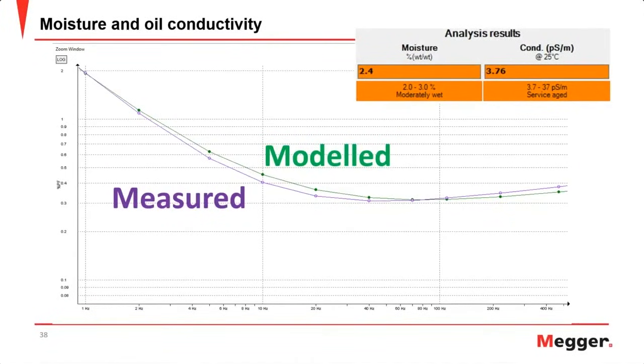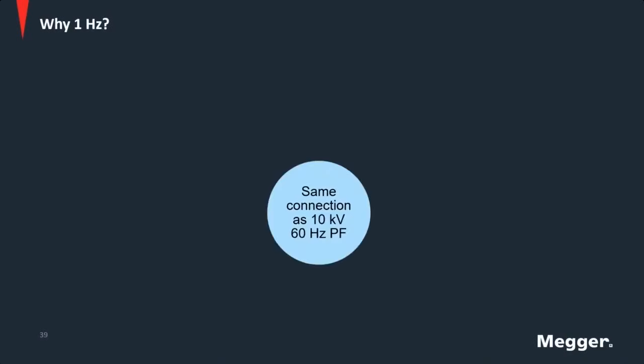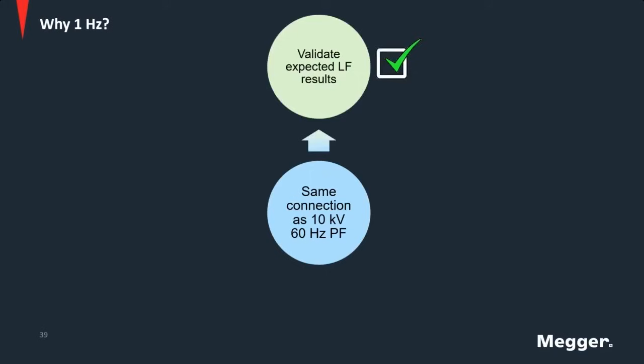What we have found is that instead of using this entire dielectric frequency response range, we can hone in on the 1 Hertz value. And the 1 Hertz can tell us a little bit of information. And when we look at 1 Hertz, what we can do is, using the same connection that you're already using today for your 10 kV 60 Hertz power factor, we can also perform the 1 Hertz test. And our software today is automatically configured to run 1 Hertz and also run ITC. And what we see is that with the 1 Hertz value, we can validate your expected line frequency 60 Hertz results.